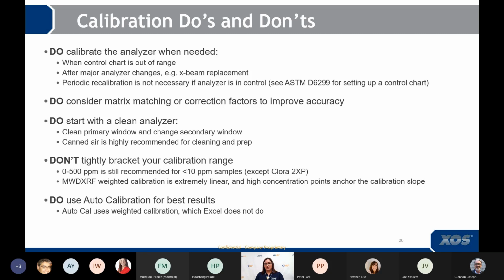One of the things that might be a little bit new for some folks, especially if you've been in the industry for a long time working with X-ray analyzers: it's typical that you would tightly bracket your calibration. So if you're only going to run a 10 ppm sample, you wouldn't calibrate very high, you would tightly bracket it. But this actually is not what you should do when you're working with a Sindie or a Clora analyzer. We still recommend the 0 to 500 ppm calibration when you're running those 10 and 15 ppm samples. And the reason for this is that these analyzers use a weighted calibration. It's extremely linear. I'll talk a little bit more about that.